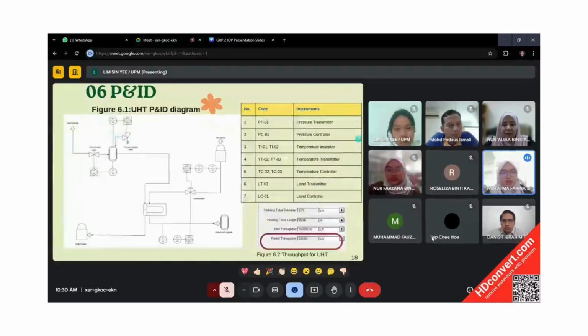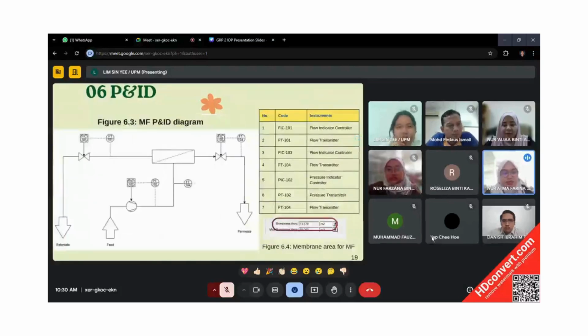The second one shows the P&ID for microfiltration. The microfiltration process has 3 main flow streams: the feed, the retentate, and the permeate stream. The feed enters through the inlet with its flow rate measured by flow transmitter FT101 and regulated by flow indicator controller FIC101 for steady input. A pump pressurizes the feed, with its pressure monitored by pressure transmitter PT102 and controlled by pressure indicator controller PIC102.